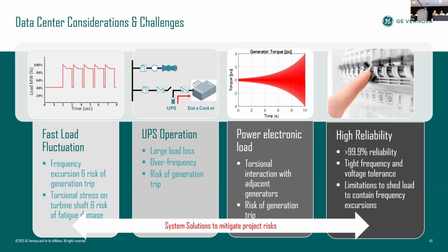And there's another characteristic of the load that we need to understand: power electronics load represents a large portion of the data center load, and this load tends to have very low damping, right? Because it's a constant power, constant current type of load, it has inherently negative damping characteristics, and that can sometimes trigger modes that can grow in oscillations, causing damage to the shaft of the turbine generator. Again, we are not going to talk about the torsional mode here. Last week, our colleague presented during the ESIG webinar on this topic, so I think we can go back and look at that.